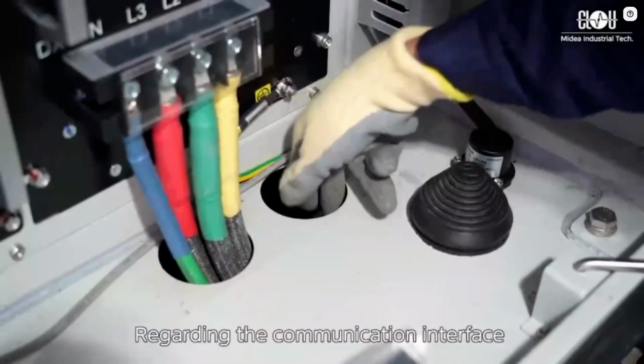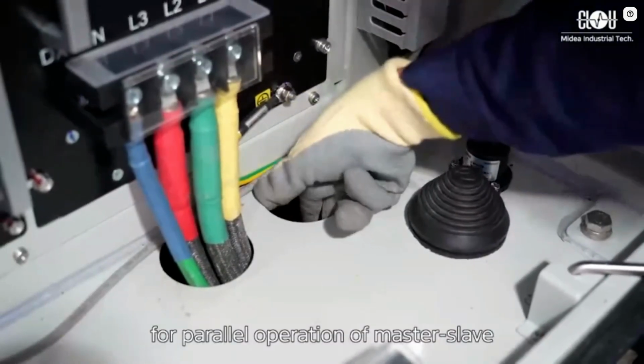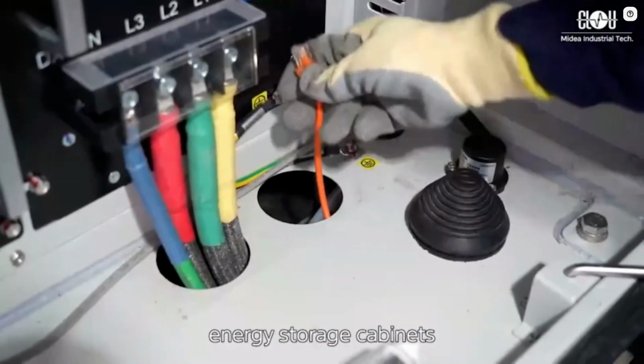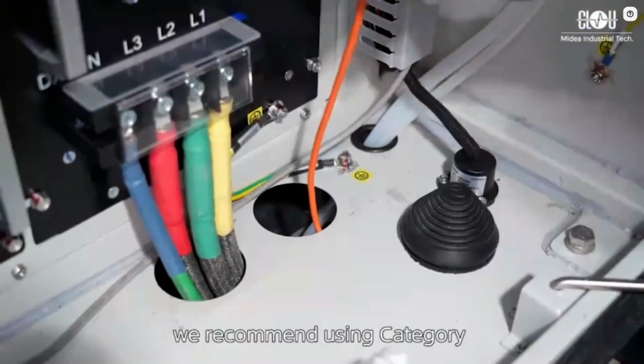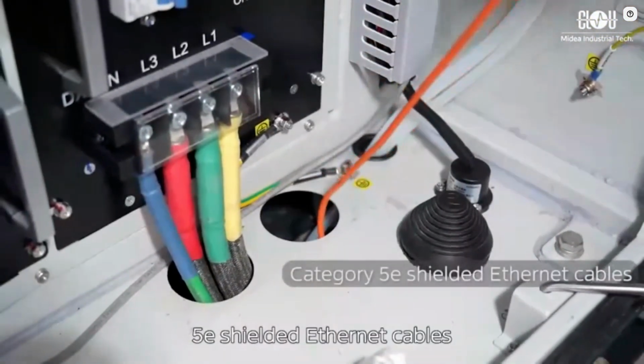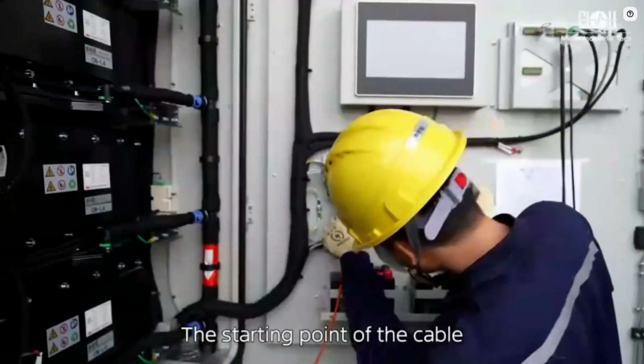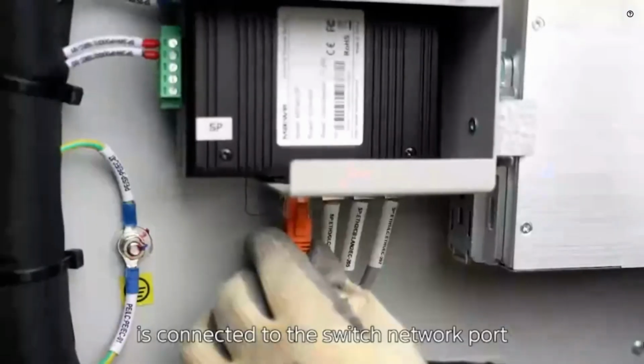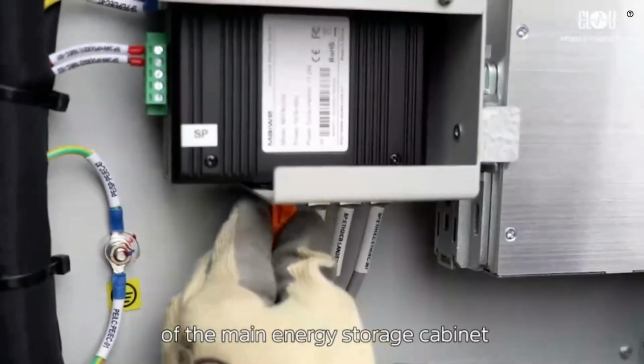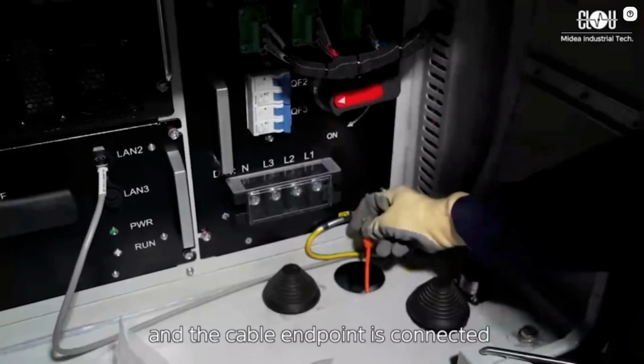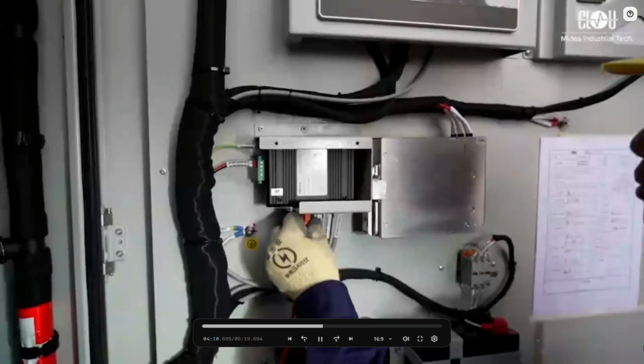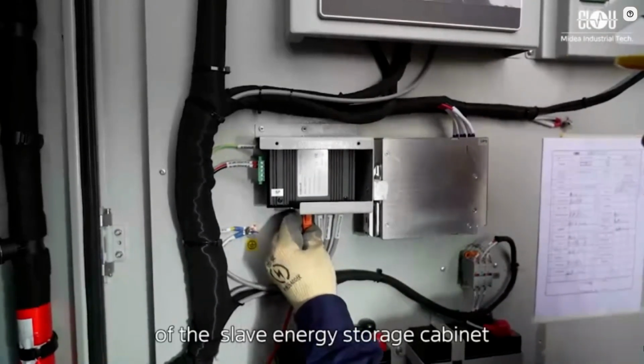Regarding the communication interface for parallel operation of master-slave energy storage cabinets, we recommend using Category 5E shielded Ethernet cables. The starting point of the cable is connected to the switch network port of the main energy storage cabinet, and the cable endpoint is connected to the switch network port of the slave energy storage cabinet.